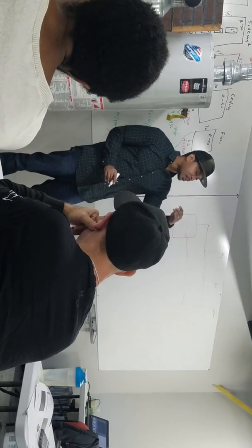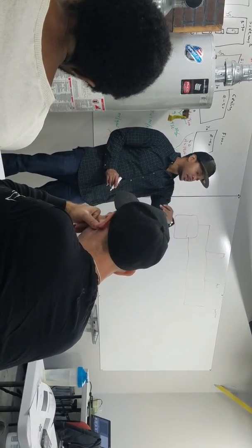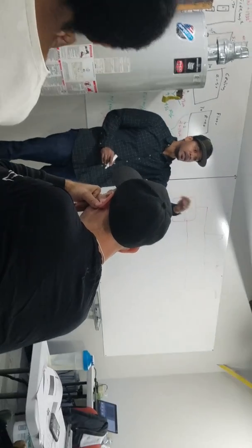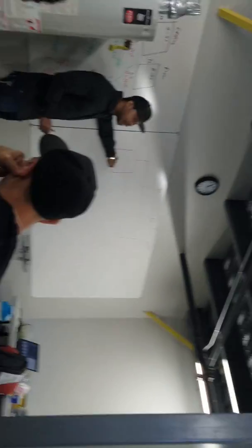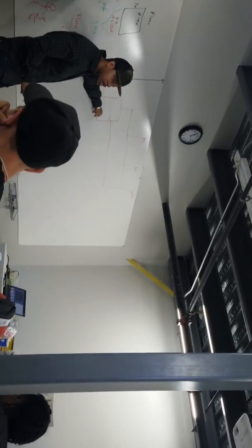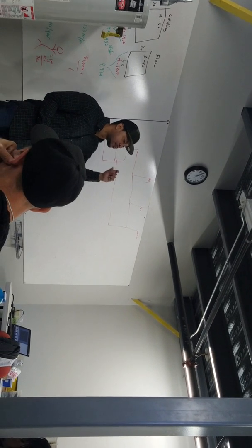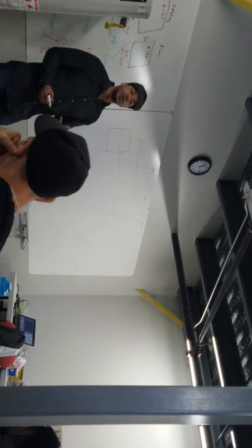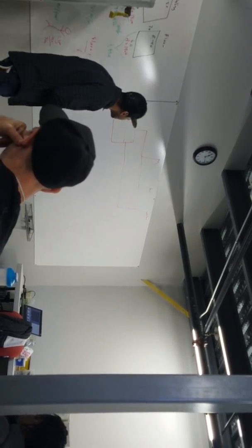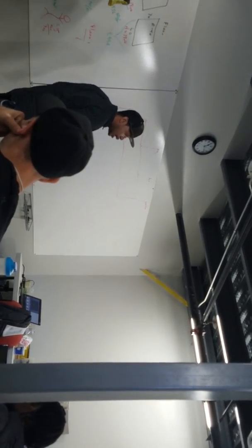It's checks and balances. One thing checks another thing, right? So back then, they didn't have all of that. So what would happen is if you caught a leak on the system, there was really no way to tell if you had a leak. The sight glass hadn't come yet, it wasn't invented yet. So there's really no way you could tell you had a leak. And what would happen is boilers would run out of water. And you wouldn't even know it. And the boiler would be burning and firing dry.